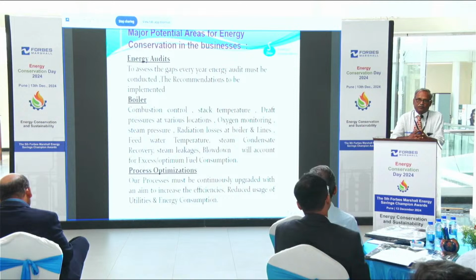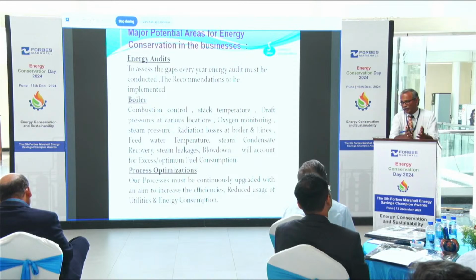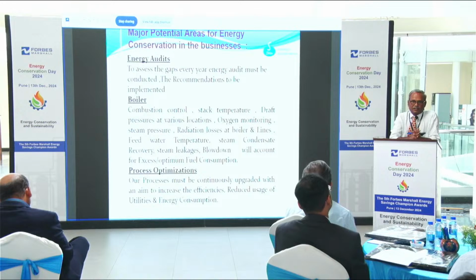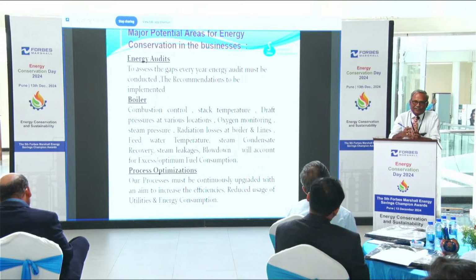Since 2009 we've been working with Forbes Marshall on steam distribution and condensate recovery, and they are working well. We have about 250 steam traps or line traps in our plant. Last year when QV audited that, out of 250, about 35 were not working on the line traps because accessibility is very limited on the pipe tracks. So the traps got stuck, and no investment is required, just servicing of the traps.